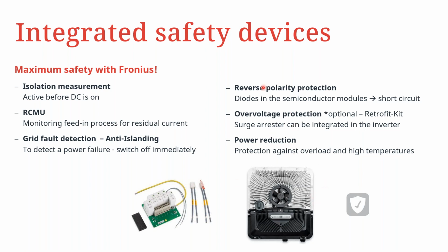We also have reverse polarity protection. This is done through diodes. We have also over voltage protection as an option. So we have said these are available as retrofit kits. And then we have the power reduction, depending on the temperature of the inverter. Then the inverter is able to reduce the power output to prevent damage to the electronics inside.